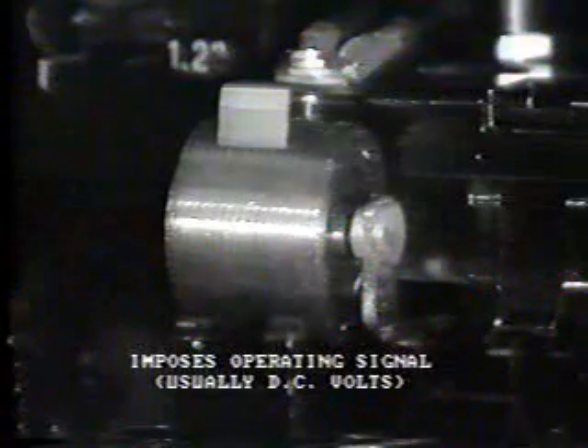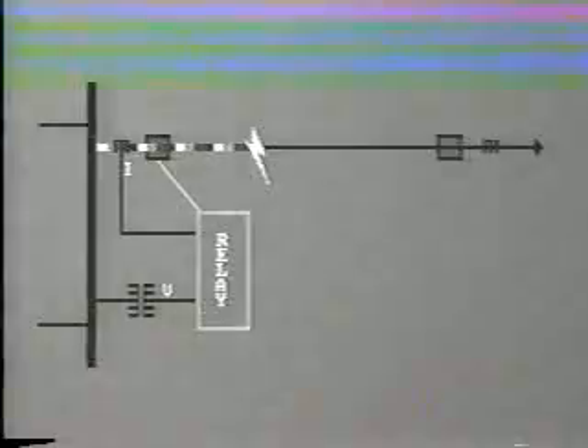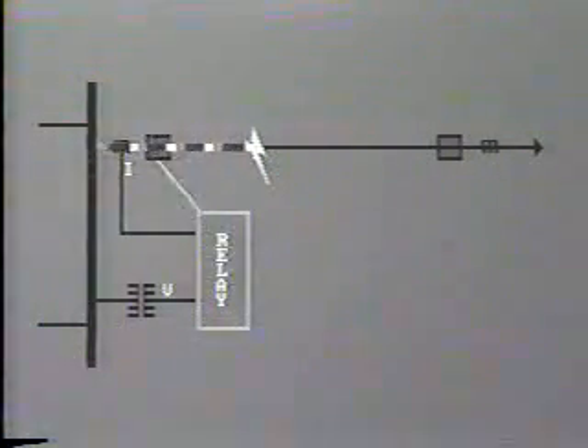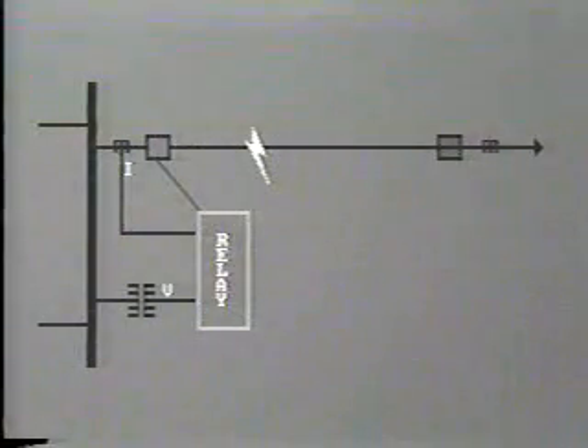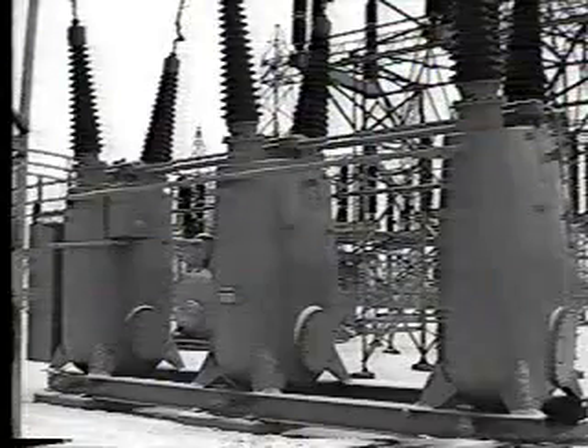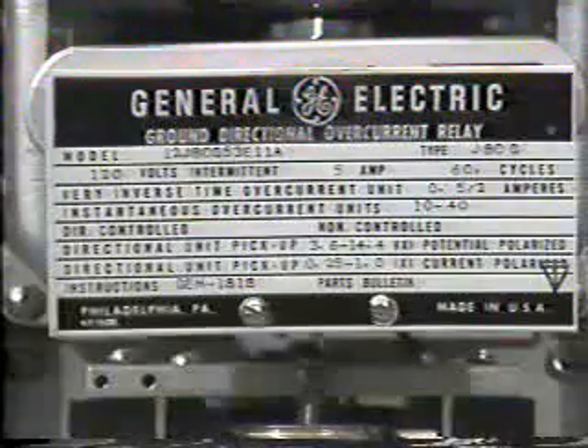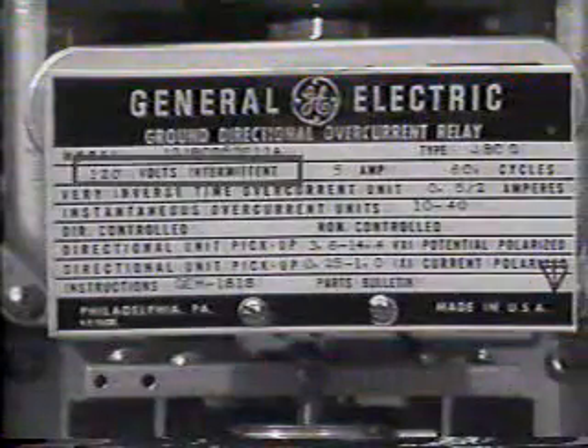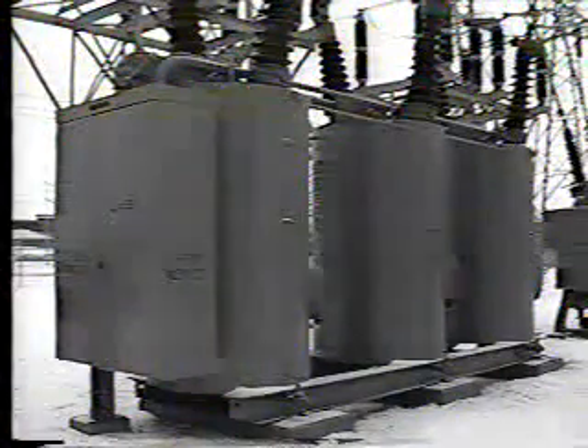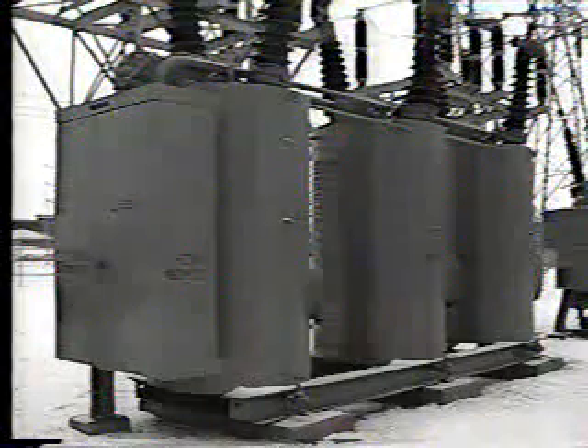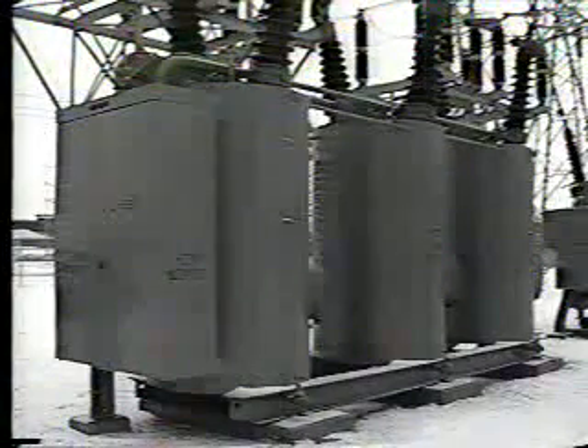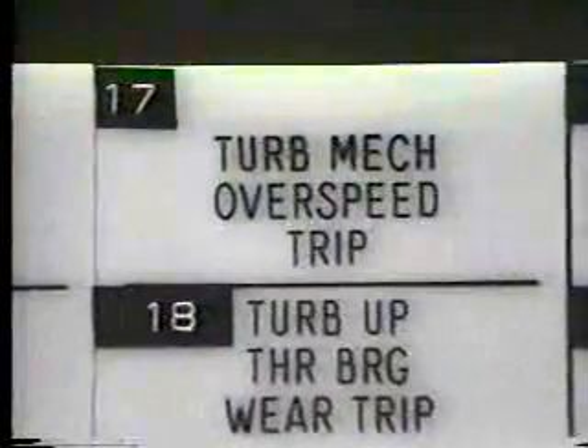However, with an intolerable fault level, then the relay output will impose an operating signal on a control circuit, usually in terms of DC volts. This tripping signal is then fed to one or more circuit breakers to cause them to open so as to isolate the faulty circuit. What is the purpose of the circuit breaker? Well, obviously, the relay itself is a small, low-voltage control device, whereas the circuit breaker is an integral part of the high-voltage, high-current power system. In fact, for the protective relay to have any impact at all on the power system, it must be coupled to a switching device. The exception to this is where relays are used to give alarm only. But for action, it must command a switching operation.